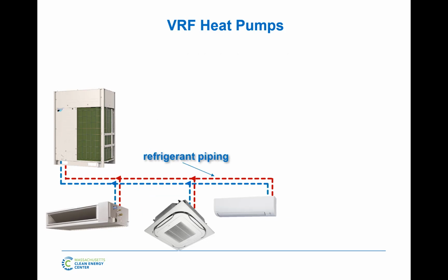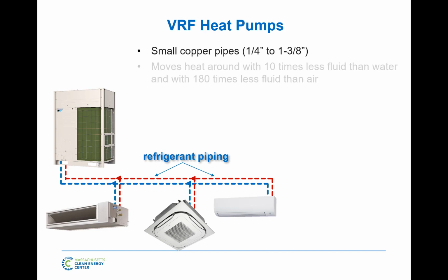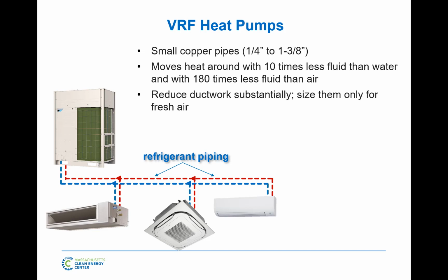Then you've got refrigerant piping that connects all these indoor units back to the outdoor unit. We'll talk about this a little bit later, but the fact that we use refrigerant to move heat around the building means that we can move the same amount of heat in a lot smaller volume. So what that means is you'll see later some of the flexibility of VRF is I'm just putting little pipes around the building instead of larger water pipes or instead of large ductwork.